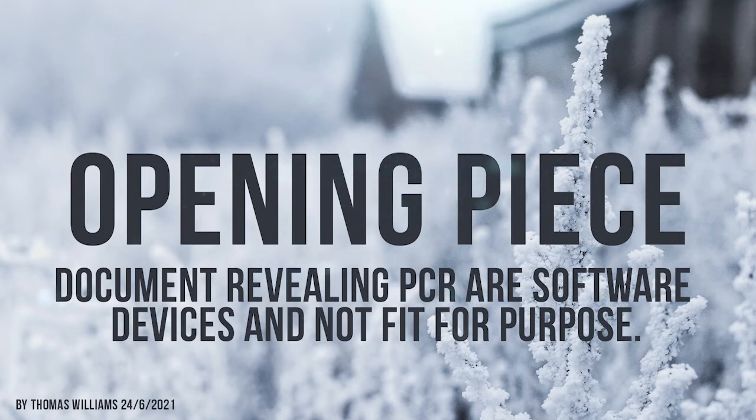The FDA determined the cause was software design. On the 1st of January 2021, Biomeme Inc issued an urgent device recall correction with the latest build of the Franklin real-time PCR thermocycler, which affects some devices built since September 21st 2020. This software correction is to fix an issue where the device is unable to get past the beginning stages of the test. It was distributed in Florida, Texas, Indiana, Kentucky, Ohio, New York, California, Pennsylvania, Maryland, and also Canada and Zimbabwe.